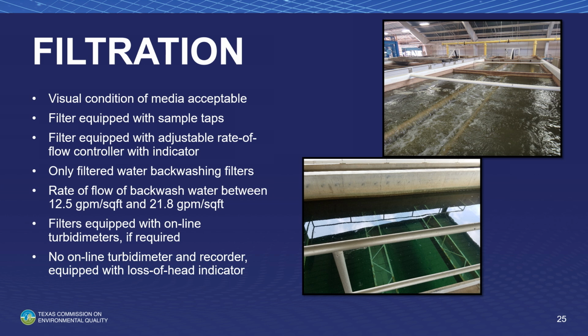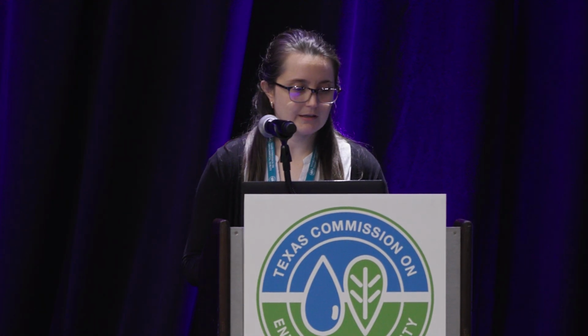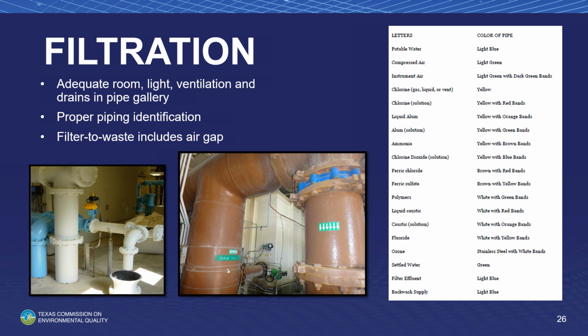And having your filters equipped with online turbidimeters if required, and if no online turbidimeters, the recorder equipped with a loss of head indicator. Most filters nowadays are going to have the online turbidimeter on it, but if you're still running a relatively older plant, you may be working off a loss of head indicator.